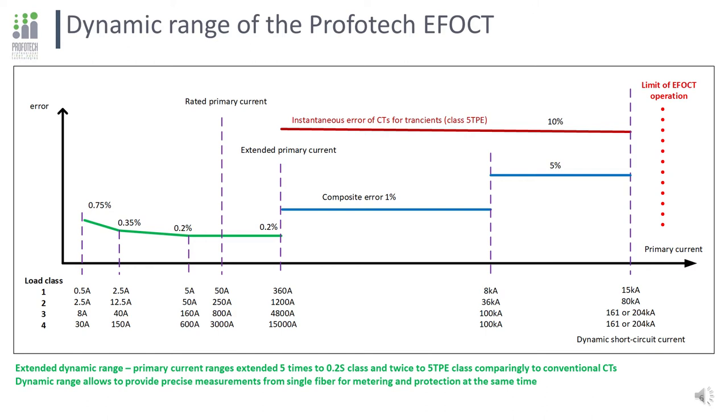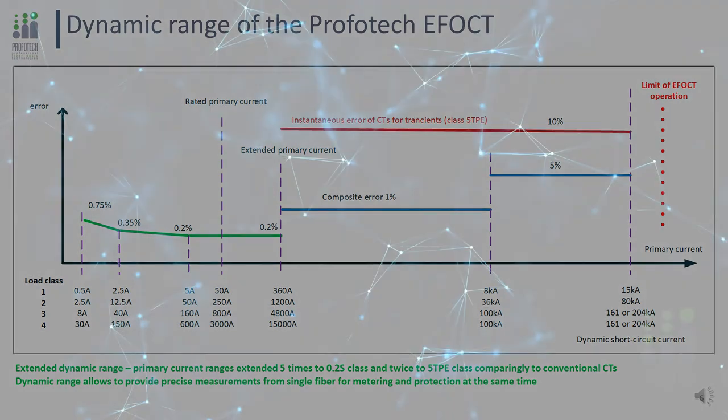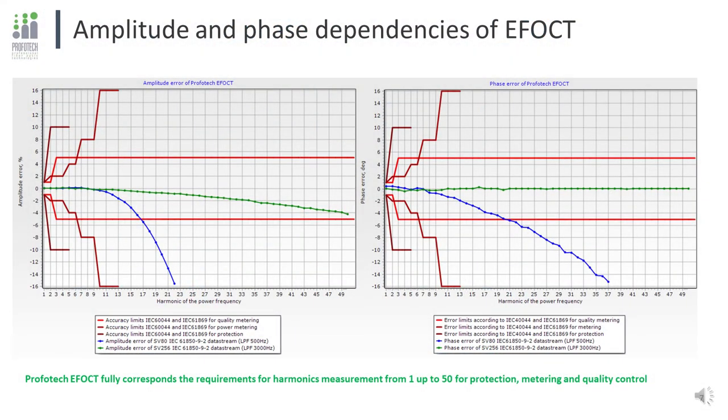We believe we no longer need 20 to 30 different transformers for different rated currents — only four load classes will be enough, which is much easier for substation design and operation. The next critical point is amplitude and phase dependencies when measuring harmonics. The principle of the Profotech EFOCT is very fast and precise measurement of the instantaneous value amplitude. All points are measured in DC mode independently from previous measurements, giving ideal amplitude performance with zero phase error in harmonics and transients. The figures show accuracy limits for protection, metering, and quality according to IEC 60044 and IEC 61869.